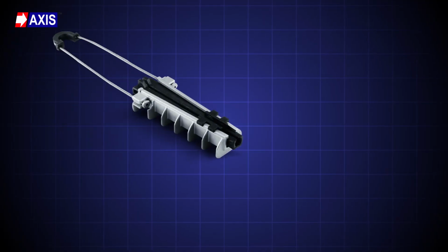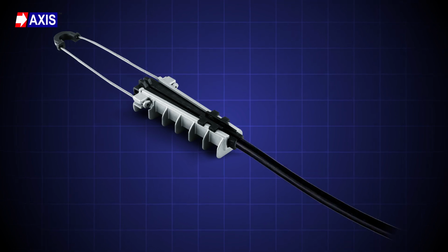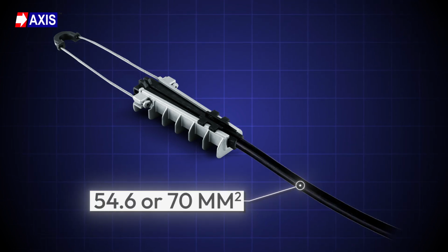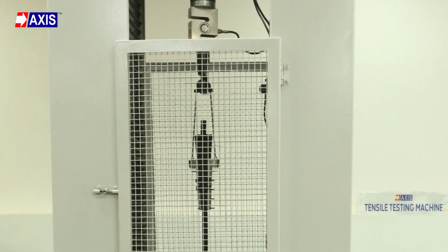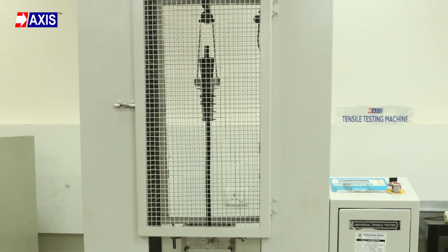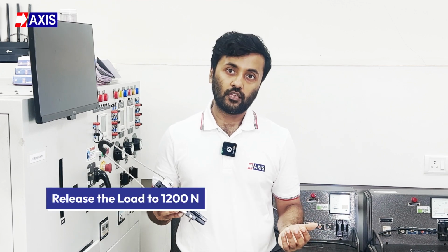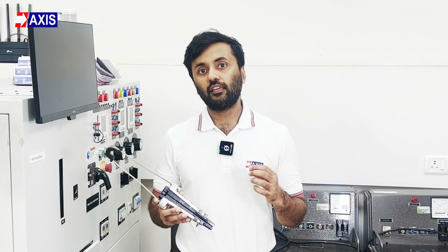This checks if the clamp can hold the messenger wire under tension without slipping or breaking. So how do you conduct this test? Use an anchoring clamp and fix it to a neutral messenger cable of 54.6 or 70 mm square. Place the setup in a UTM machine. Now, apply the following load sequence. First, apply 4800 newtons of force, then release the load to 1200 newtons. Mark the messenger cable at the point where it exits the clamp. This marking helps measure any slippage with respect to the clamp.